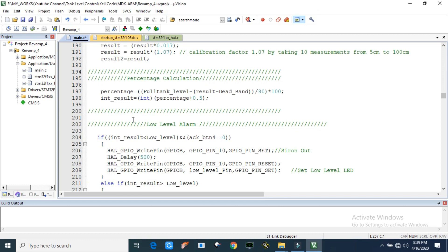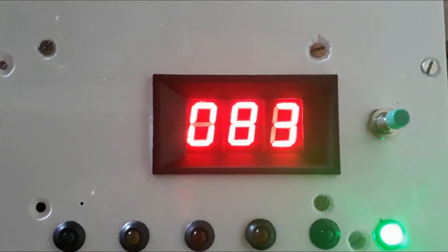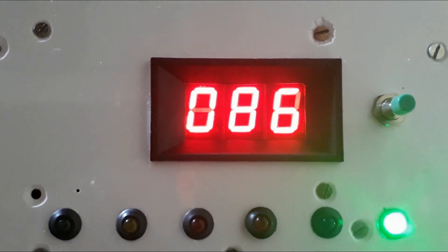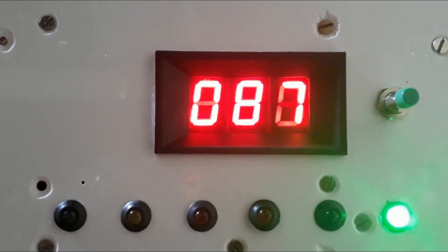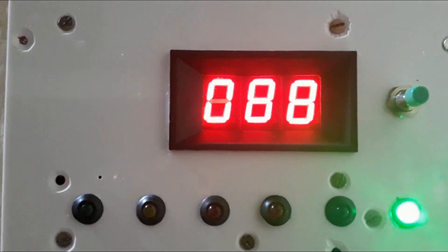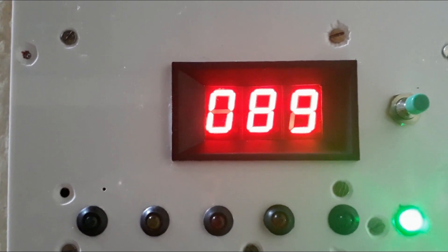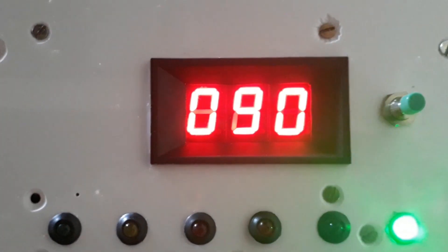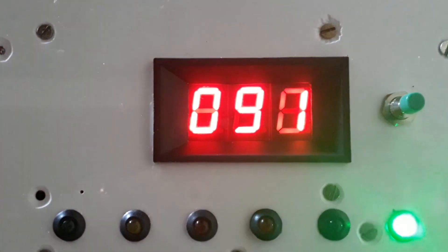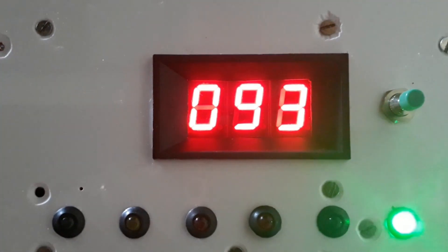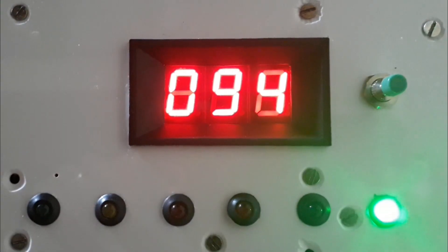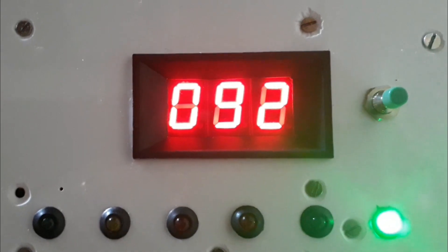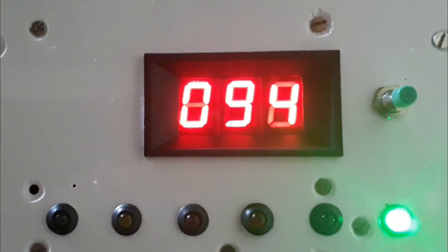Then we can check the working of the actual system. We power on our system. You can see the current level is about 82-83%. Water pump is working, tank is filling up. We can see the level is also increasing. You can see some fluctuations in the level while tank is filling. This is due to the reverberation of the water surface. The reverberation may happen because the water is discharging from the pump. So some fluctuations in the water level are there, and corresponding reading is also fluctuating here.